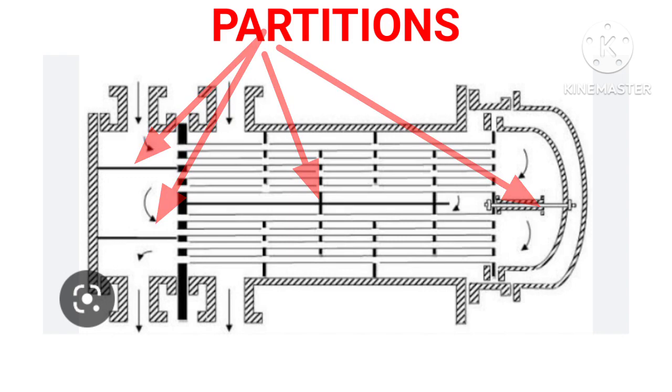Hence, multi-pass construction decreases the cross-sectional flow path, which increases flow velocity. Due to this, heat transfer coefficient also increases. But these also have certain disadvantages, such as multi-pass construction becomes complicated and also creates high friction losses.